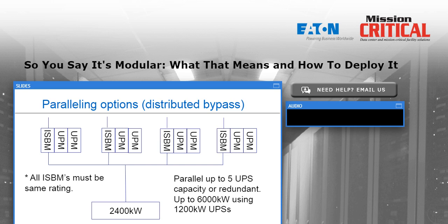In some cases, if you have more than 3 UPMs, a traditional system with a centralized bypass may be the most cost-effective. If I have 2 or 3 UPSs in parallel, I might save some money to go with the distributed bypass. We should comment the distributed bypass is far and away the most commonly deployed parallel system around the world from every UPS vendor out there.